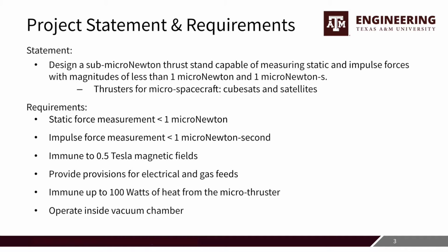The requirements for this design are as follows. It must measure static forces less than 1 micronewton as well as impulse forces less than 1 micronewton second. It must be immune to magnetic fields of up to 0.5 teslas. It must provide provisions for electrical and gas feeds, as well as be immune to up to 100 watts of heat during testing. And lastly, it must successfully mate to a 14-inch steel flange for vacuum testing.